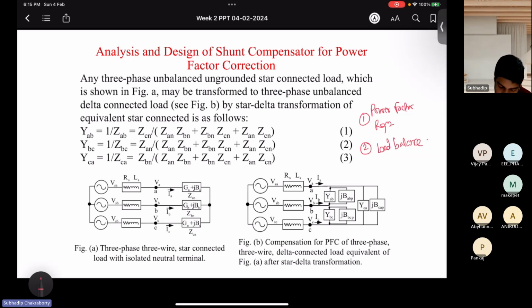But one thing, can you tell me, in a three-phase, three-wire system, can neutral current flow here, even if there is unbalance? For example, IA not equal to IB not equal to IC. This is the meaning of unbalance. Will this lead to neutral current?